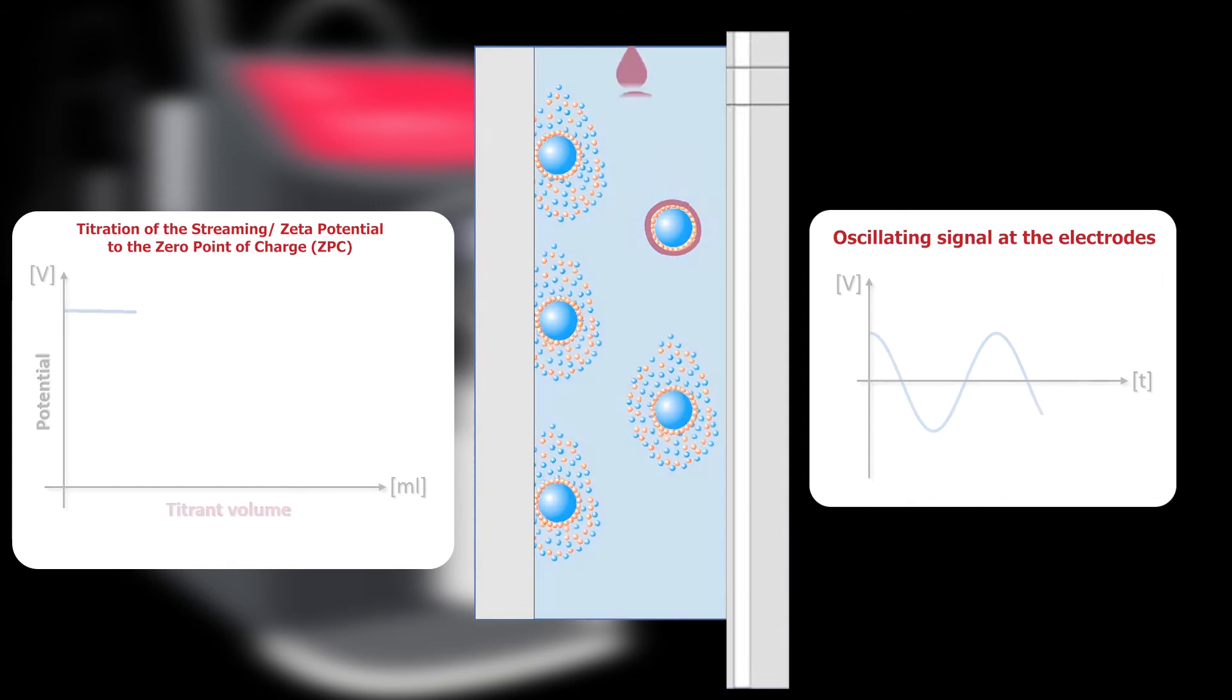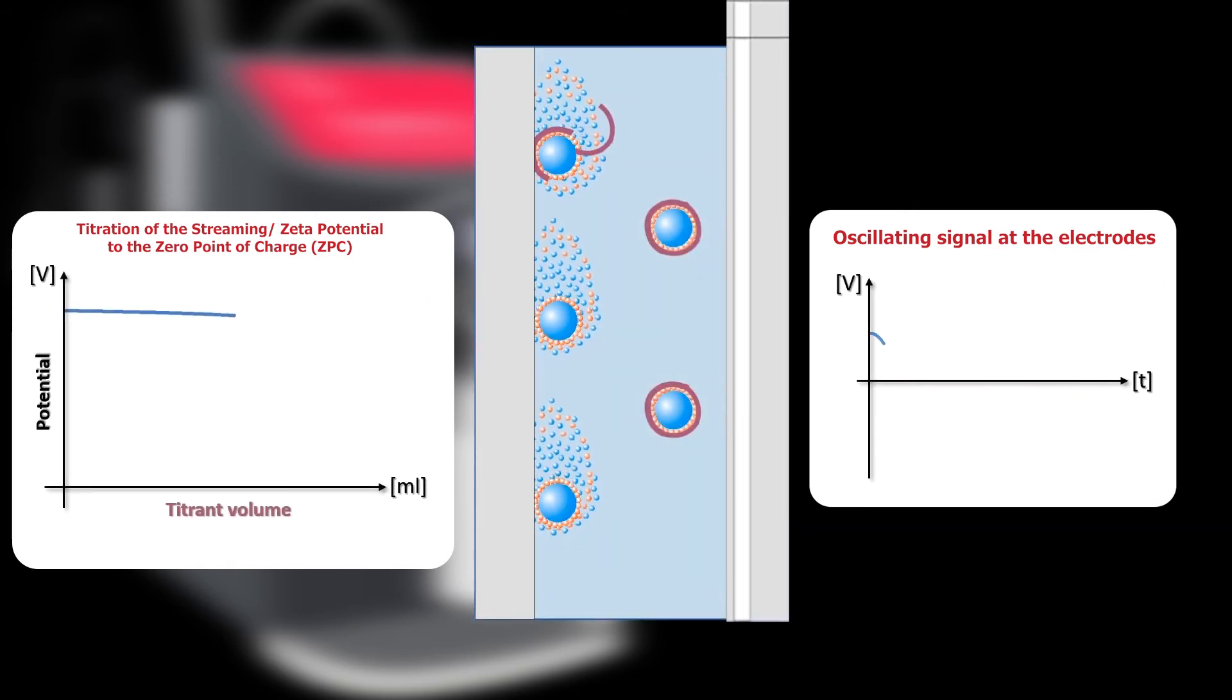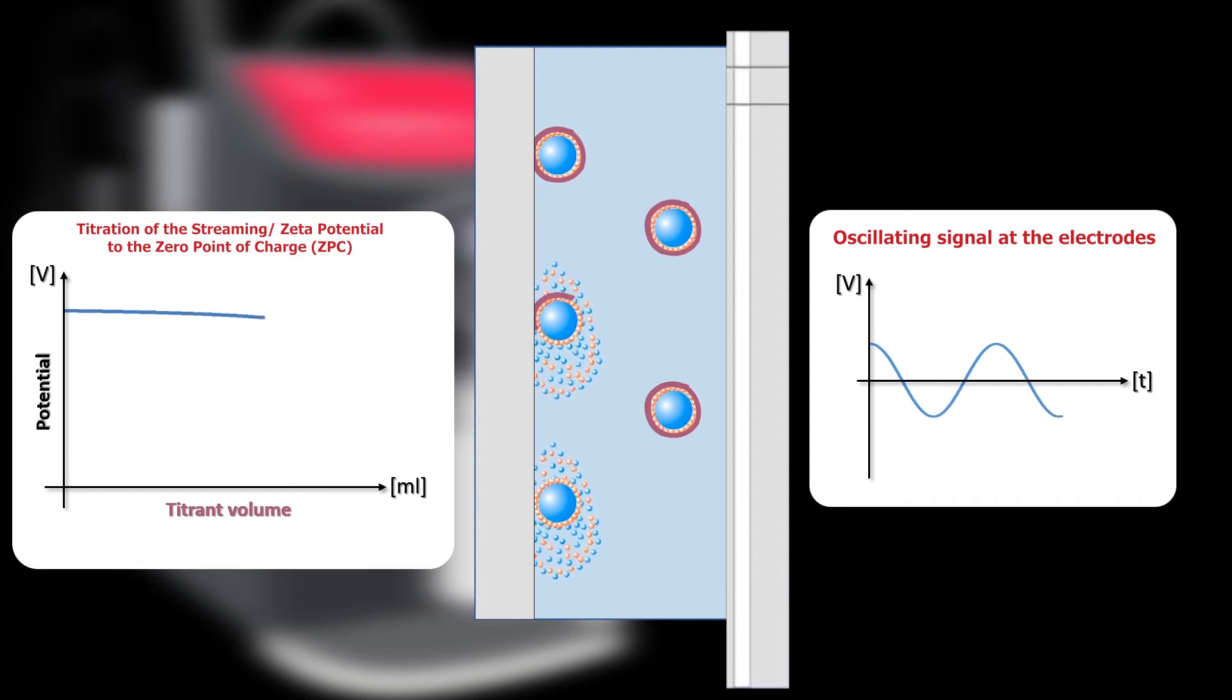To determine the true stability, we track changes in zeta potential against the volume of titrant added, thus allowing calculations such as isoelectric points when performing pH titrations. The Stabino is a unique zeta potential instrument for analyzing and optimizing the stability of colloids and dispersions. With unrivaled technical ability when it comes to measuring streaming potential, it's able to measure sample concentrations varying from 0.01% to 40% in volume.